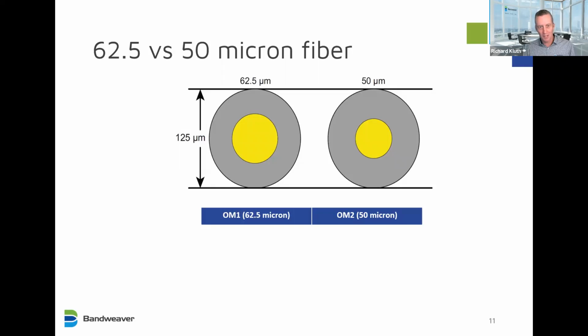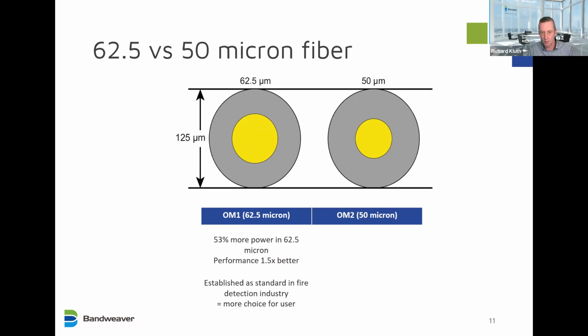Later in the presentation, I will go into more of the principles of the optics technology, but I'll start now by talking a little about the fiber optic itself. This is what carries the light, and the light is carried in this central part, the core. We use 62.5 micron, which means the part that carries the light is 62.5 microns wide. This is known as OM1 and is a telecom standard for multi-mode fiber. There's another standard called OM2, which is 50 micron, which is also used for DTS. We use it for many applications, but not in fire detection, though some of our competitors do. I'll explain why we use the 62.5. The main reason is you get 53% more power in there, so the performance is 1.5 times better. That's a real performance benefit of using the 62.5.